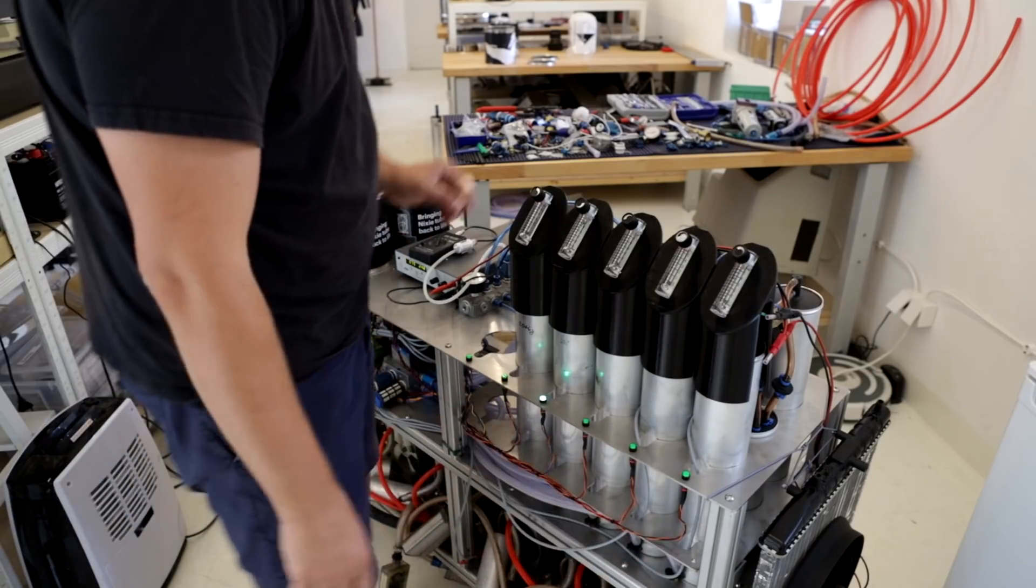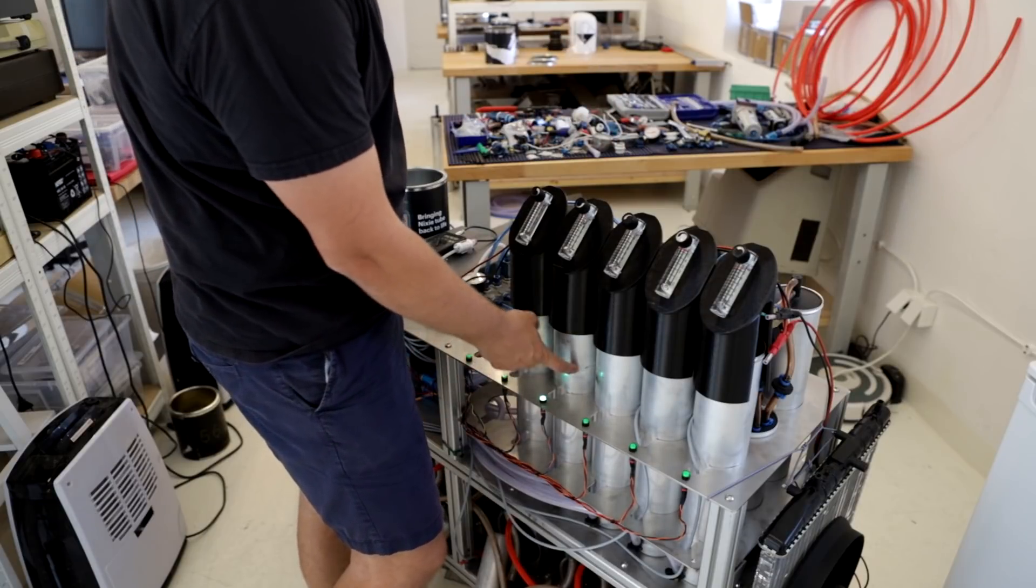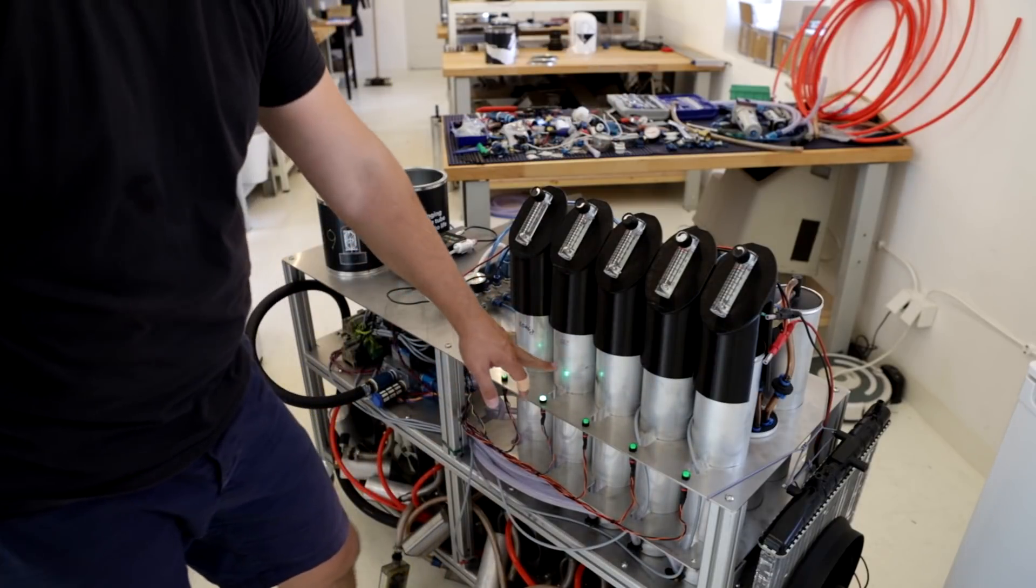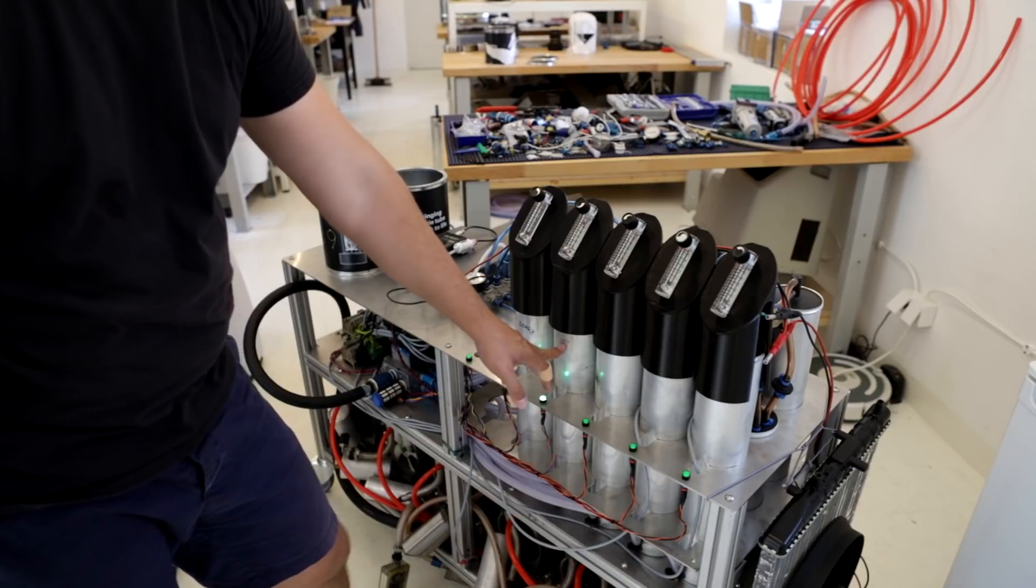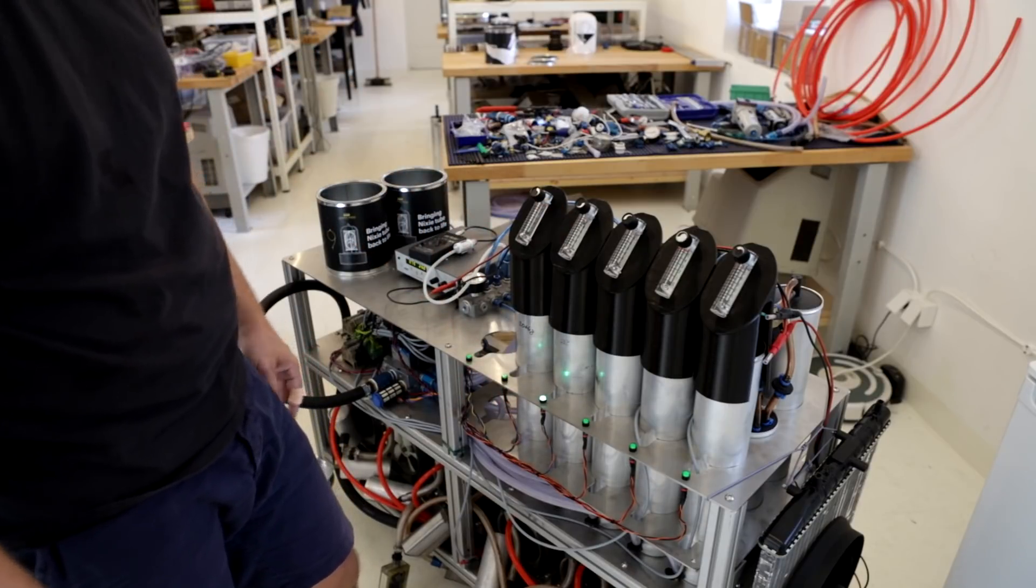So the leaks are fixed, and now I want to test the new sieves. I will pick this pair of cylinders because this one delivers only 60% of oxygen at 5 liters per minute.